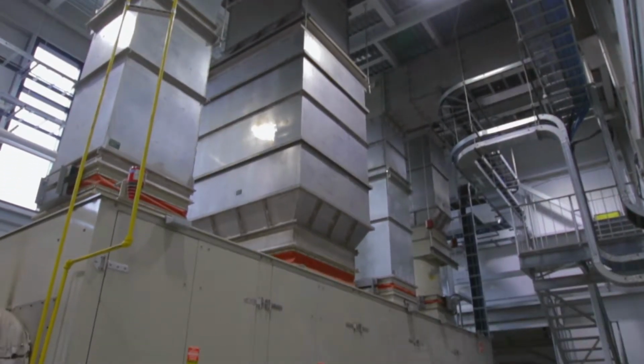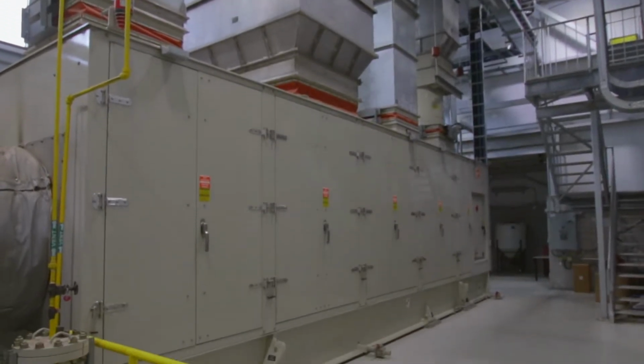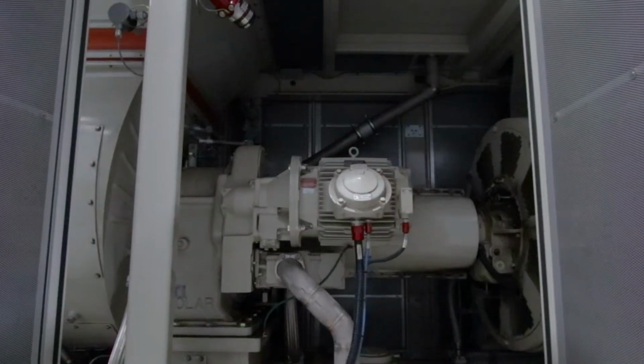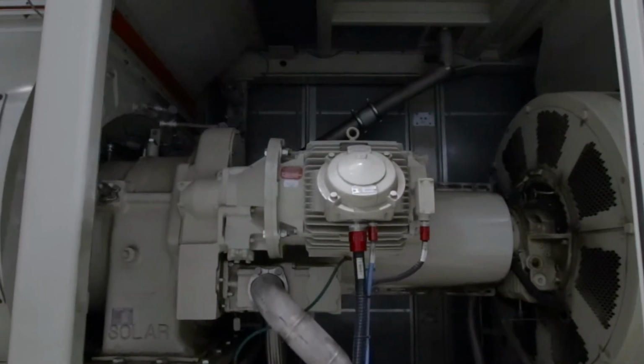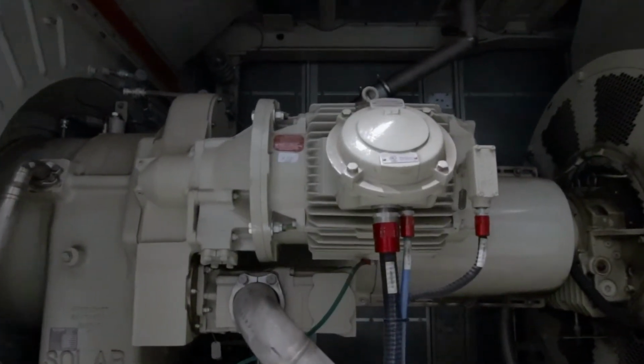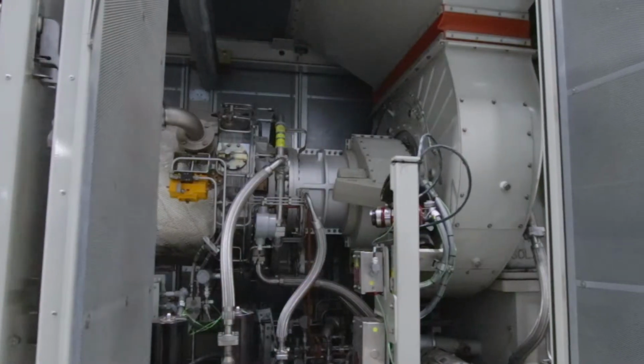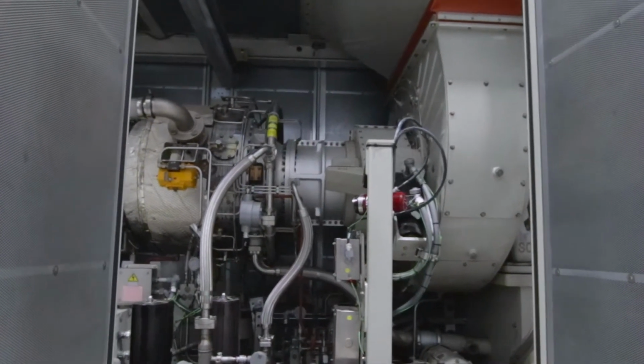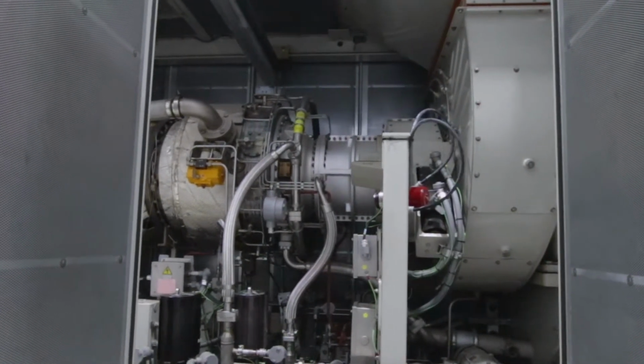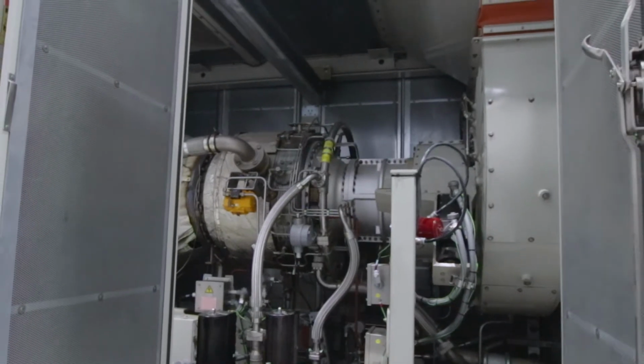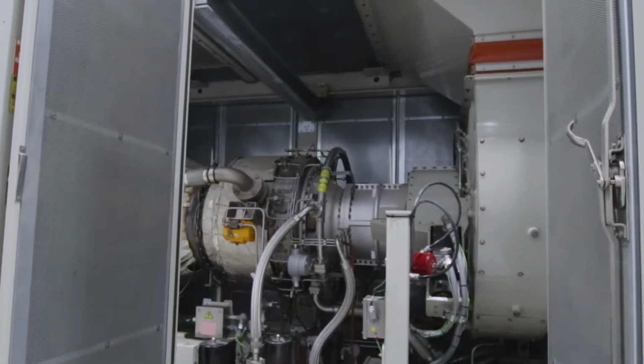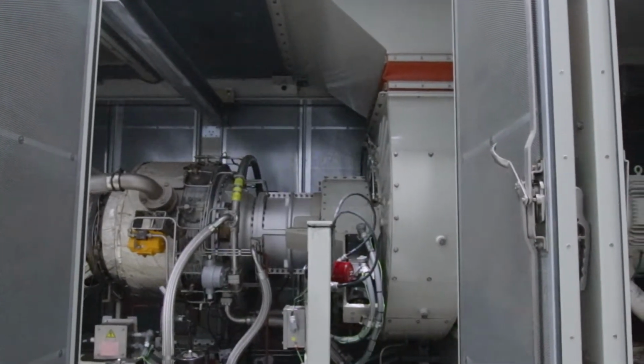Some of the unique features of this particular gas turbine is, for example, the emissions control. It has what Solar Turbines calls a SoLoNOx emissions control. It's a dry, low emissions control technology that brings down the ppm of the NOx emissions particularly, but also sulfur and carbon monoxide, in the emissions stream. And so any jurisdiction that has really tight regulations for emissions, a machine like this with the SoLoNOx control really helps meet the emissions requirements or the permitting requirements. It has a Turbotronic 5 control system, which provides a robust controller for the turbine for synchronization with the grid.